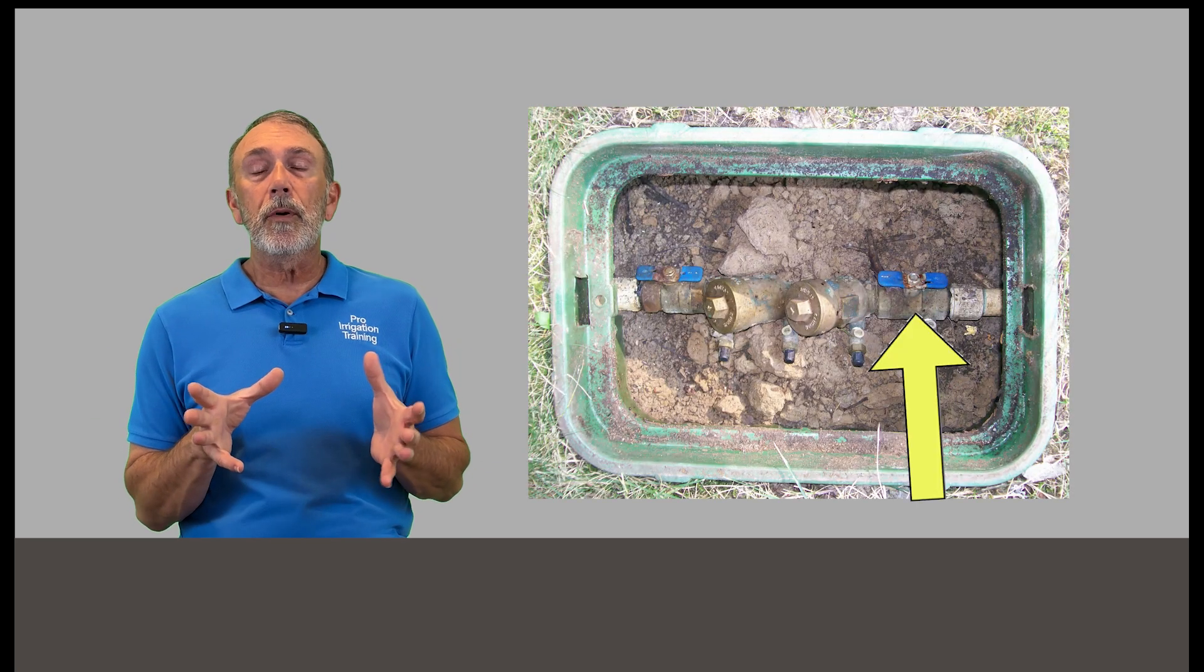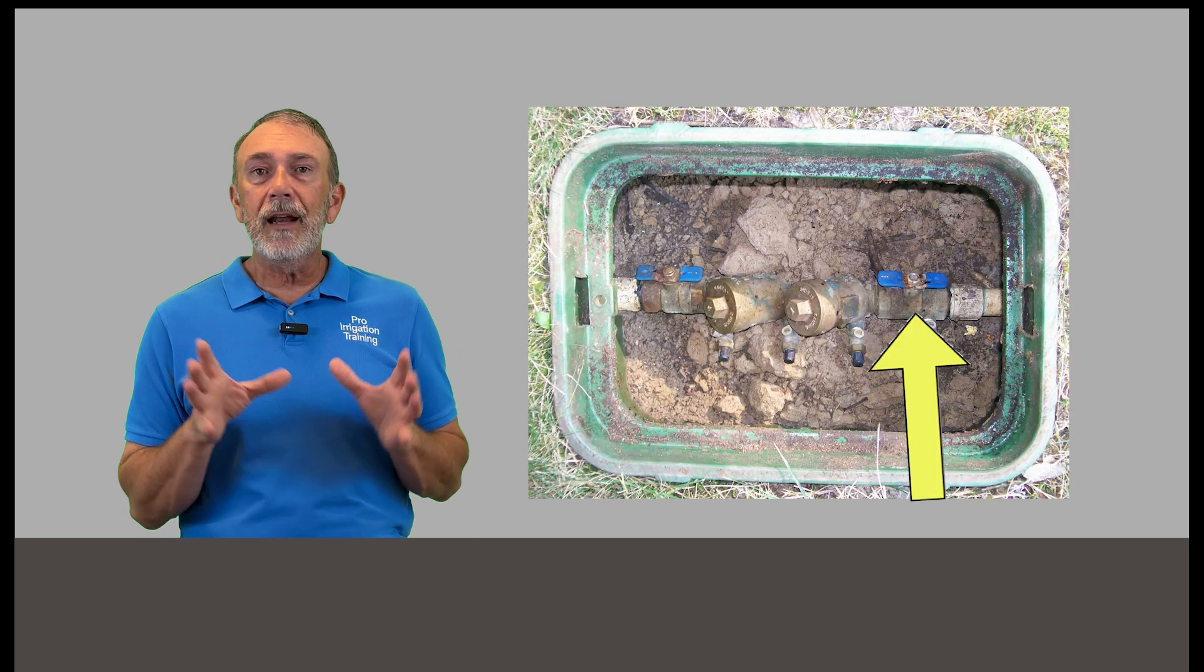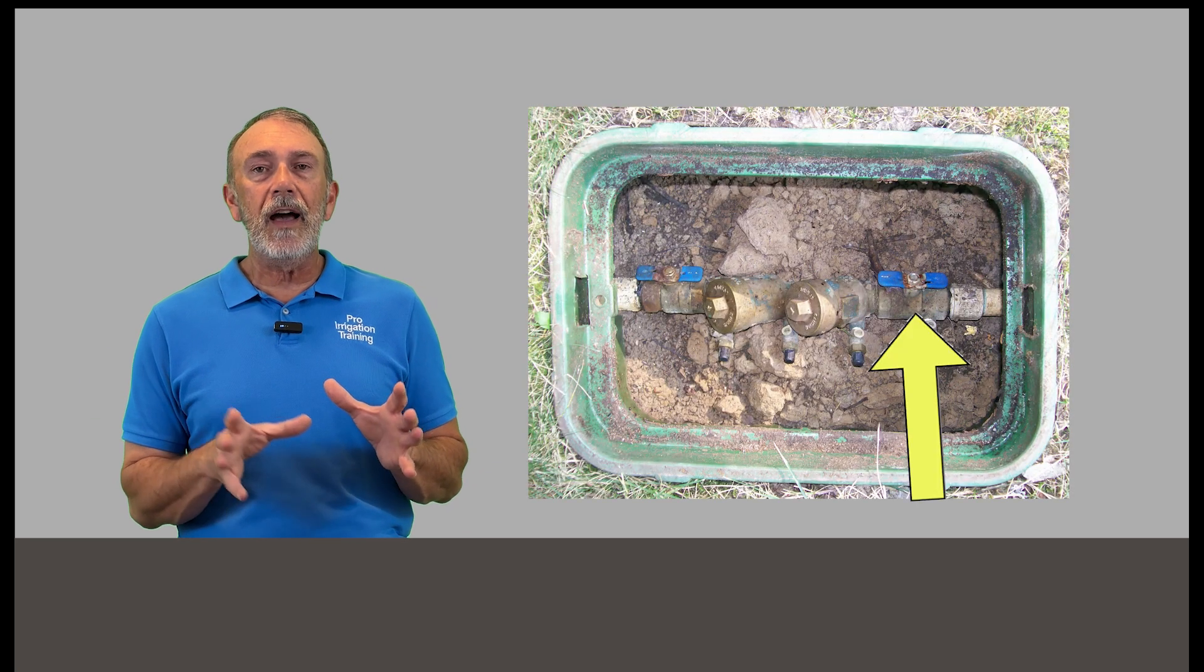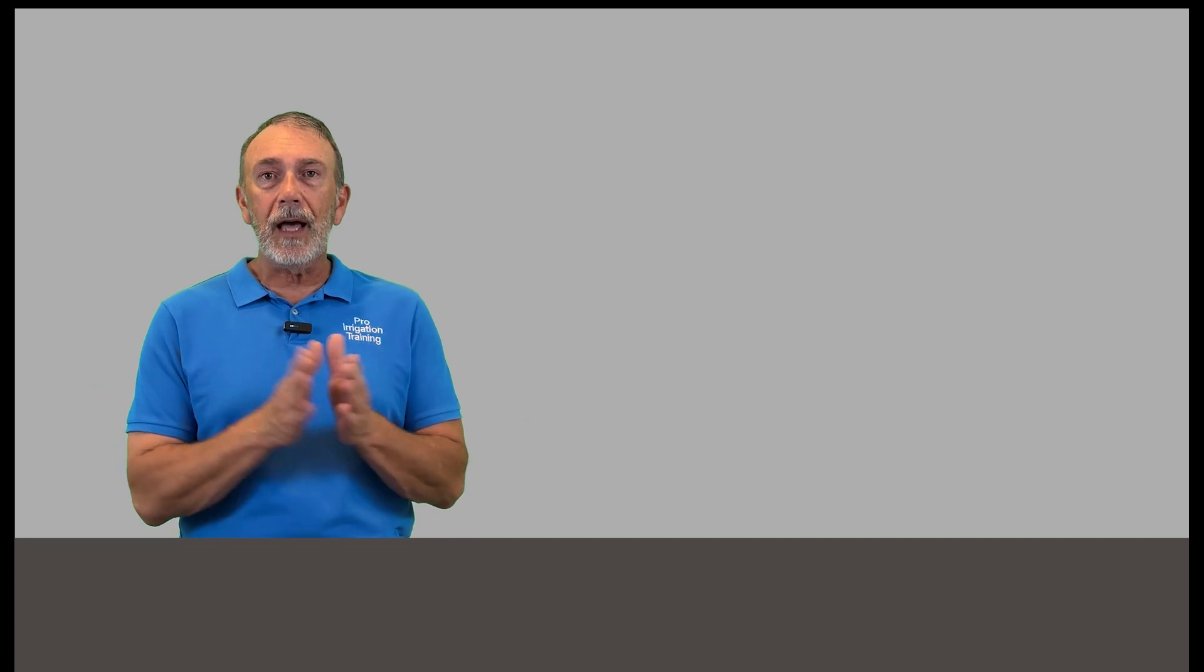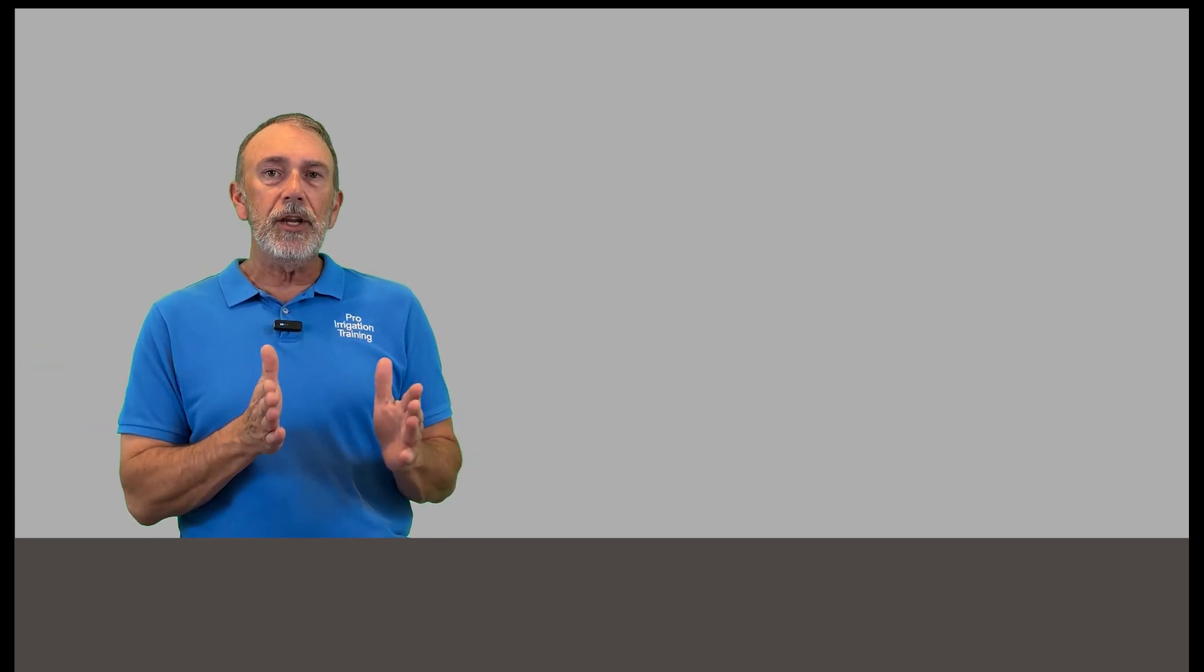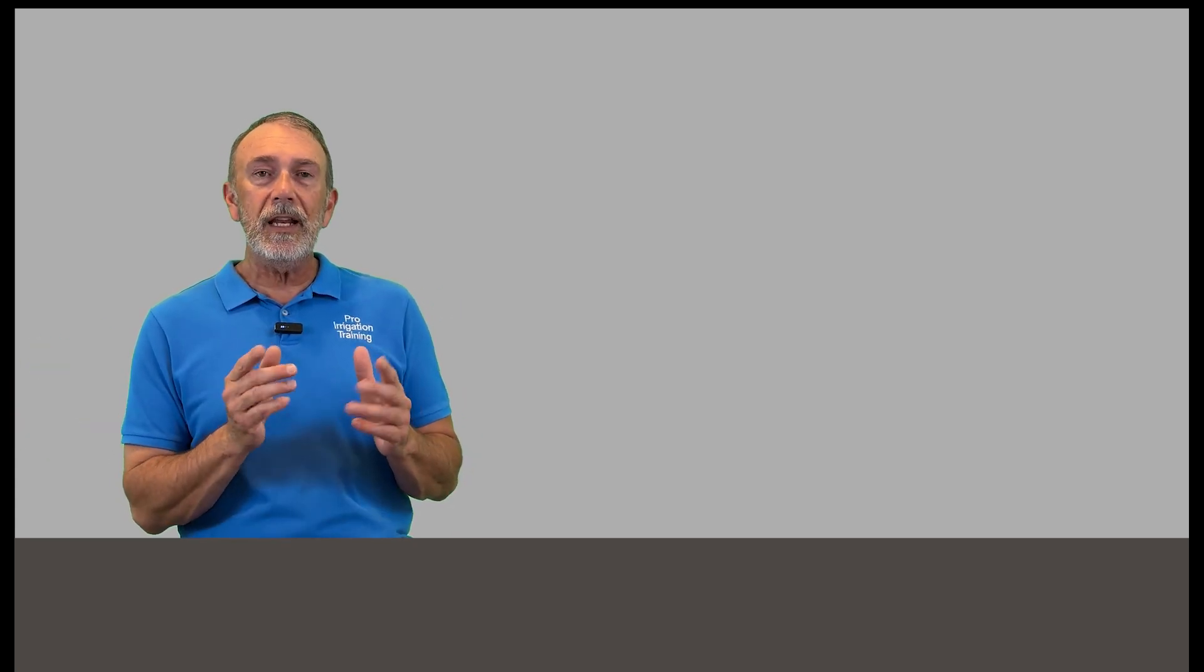If we've determined that the leak wheel is turning, we need to isolate the irrigation system from the house. So if there is a backflow preventer and there should be a backflow preventer or some kind of isolation valve on the irrigation system to isolate it from your house system, we'll close that up and then isolate the irrigation system from the house. Check your meter. Is it still turning?